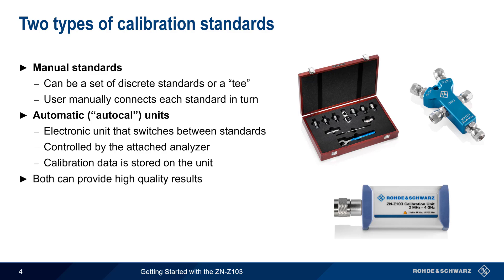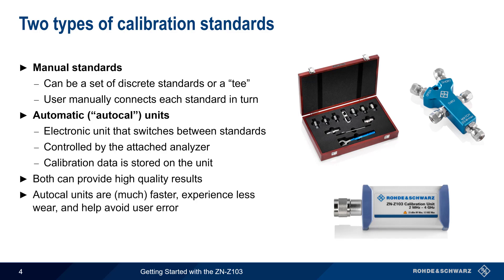When used properly, both manual and automatic calibration units can provide high-quality results, but Auto-Cal units have many advantages. They are much faster than manual calibration, they experience less physical wear, and they help to avoid many common types of user error. That said, Auto-Cal units tend to be somewhat higher cost than manual calibration kits.